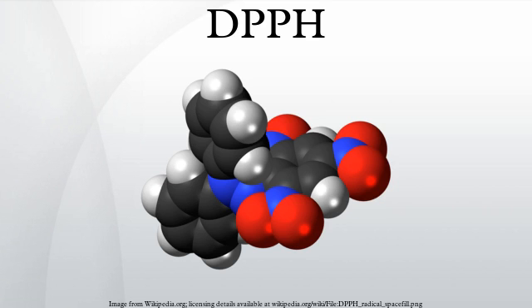The number of radicals for a freshly prepared sample can be determined by weighing, and the EPR splitting factor for DPPH is calibrated at G equals 2.0036. The DPPH signal is convenient in that it is normally concentrated in a single line, whose intensity increases linearly with the square root of microwave power over a wide power range.